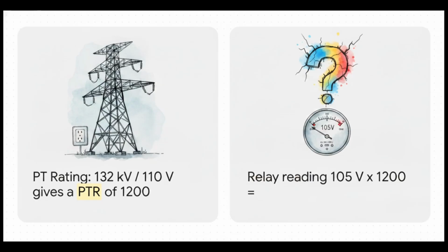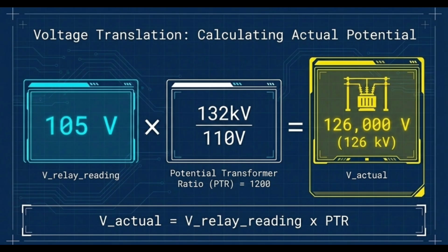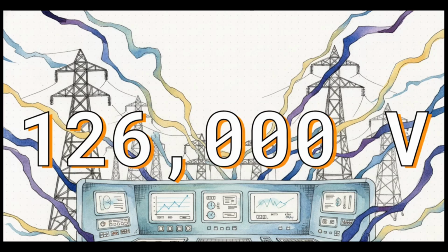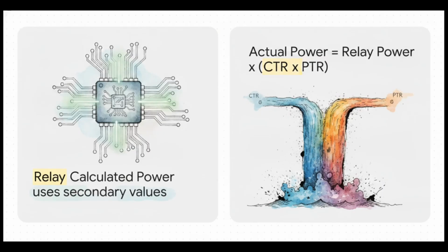Now, the relay measures a seemingly harmless 105 volts in the safe room. By multiplying that 105 volts by the ratio of 1200, the resulting calculation reveals something completely astonishing. Boom! 126,000 volts, or 126 kV. That perfectly safe low-voltage reading made inside the control room actually represents an unimaginably lethal force sitting right out on the primary busbar. And lastly, we can't forget about total power calculations.